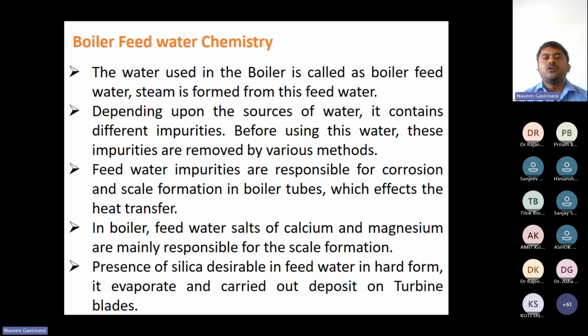Why? Because if you are not giving that much as per the design parameter, the turbine inlet valve won't open. There is a logic for the turbine inlet valve. If you bypass the valve, it will damage the turbine. So this is the most important thing. In boiler feed water, salts such as calcium and magnesium play a vital role in scale formation. We have to remove them, and also the presence of silica.